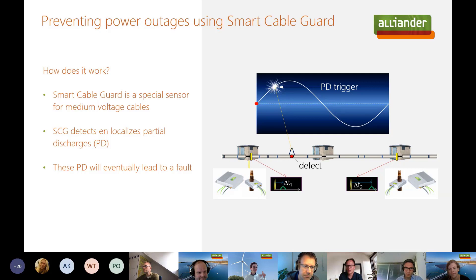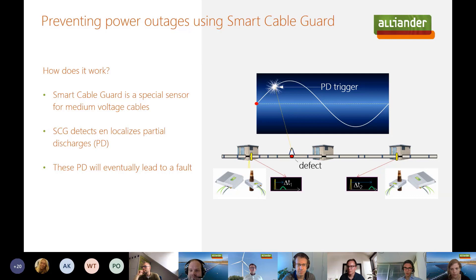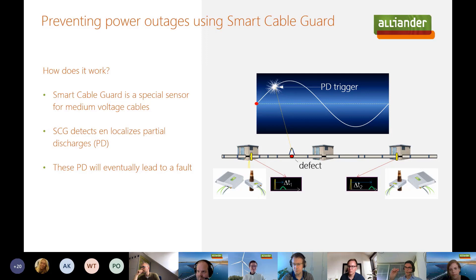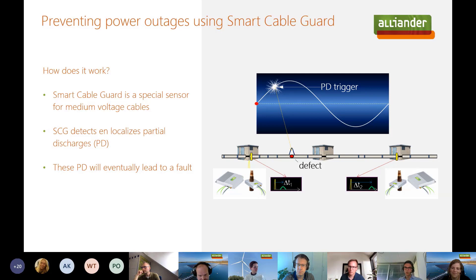Thank you for the introduction, Johan. Maybe it's good to start by explaining what Smart Cable Guard is. As a grid operator, we operate the medium voltage grid. Unfortunately, sometimes you have a power failure because a cable joint — a piece that connects two cables — breaks down. What happens sometimes before the actual breakdown is that inside the cable joint you have small sparks, called partial discharges. This can be weeks, months, or even years before the actual breakdown occurs. Wouldn't it be great if, as a grid operator, you could detect those small sparks? Then you could take preventive action and remove the joint before it fails, preventing an actual power outage. This is precisely what Smart Cable Guard is for.